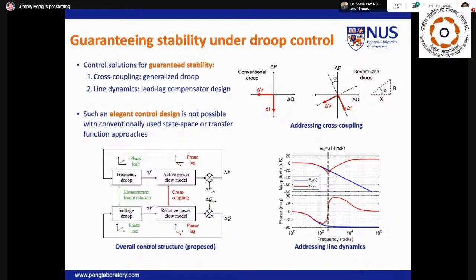This design can be directly incorporated into the existing systems without any retuning of the existing Droop values. In addition, the properties of the generalized Droop are not compromised by the design, as the filter is still dependent on rho. More importantly, the proposed filter is independent of the operating point, Droop coefficients, and the location of the source.